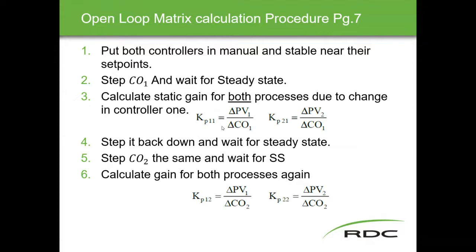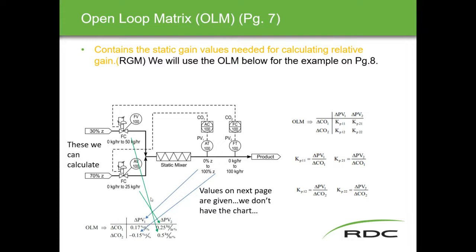To get the static gains, make a change in controller one, measure how much it affected PV1 and PV2, and divide them over each other to get KP11, KP12, KP21, and KP22. You do it first with one controller, then with the other. Looking at the PVs and the manipulated variables — the control outputs — this is where we get that data from. The OLM previously used a simpler example and walked through all the steps; the math is essentially output over input.